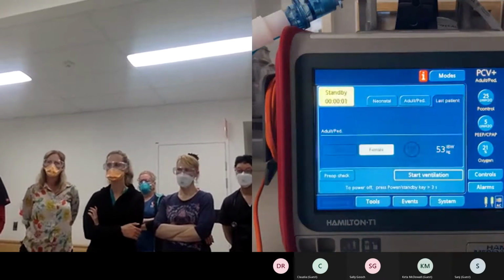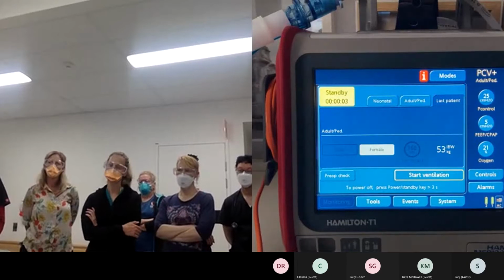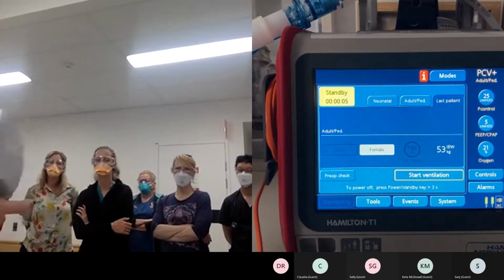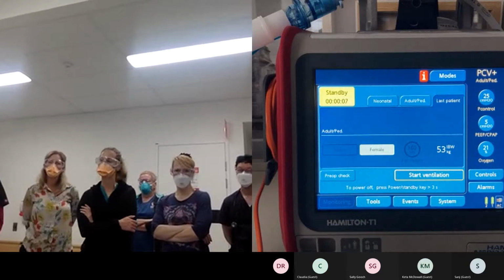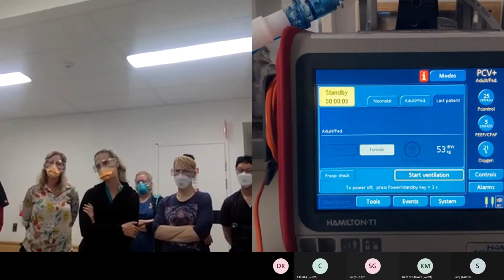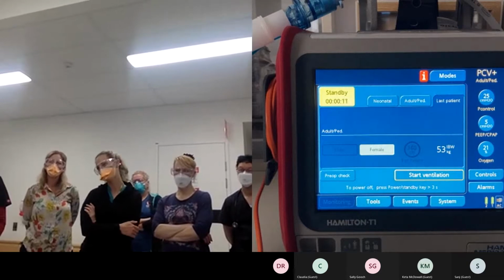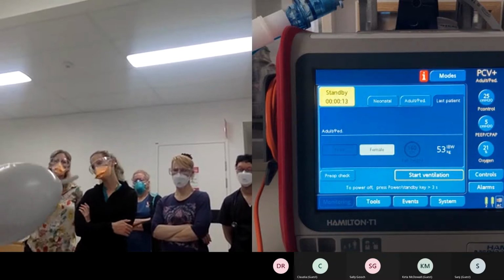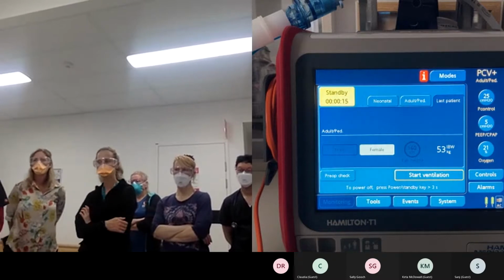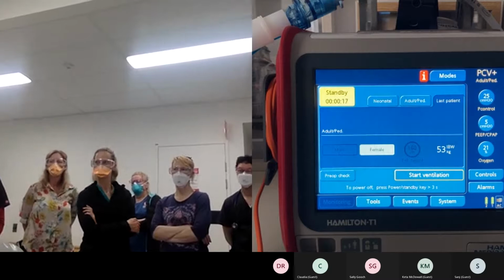Okay, if you need to come into standby, press the on-off button once, and then you confirm to activate standby. So you can't accidentally turn it off. Okay, but if you do come into standby, you have to always start it back up. So the ventilator isn't going to recognize a patient effort and start working again. You've got to tell it to start ventilation. Okay.